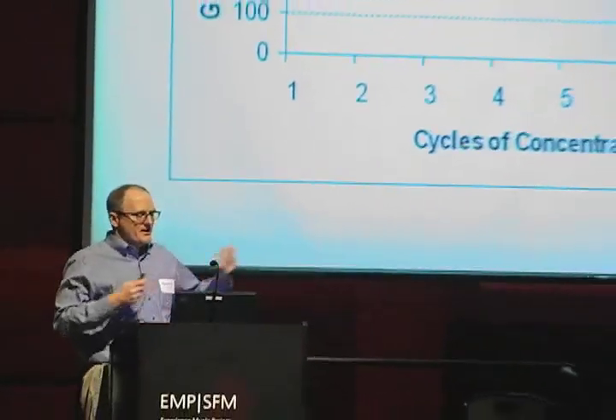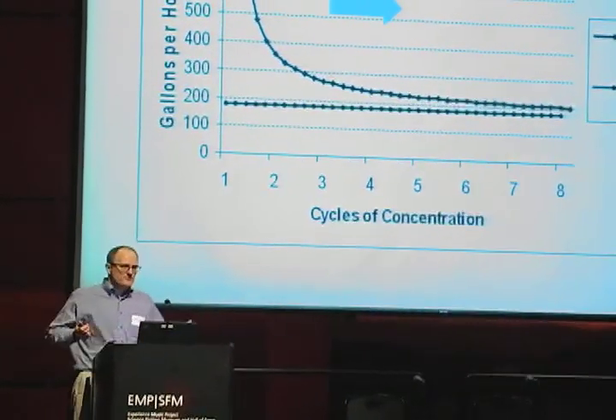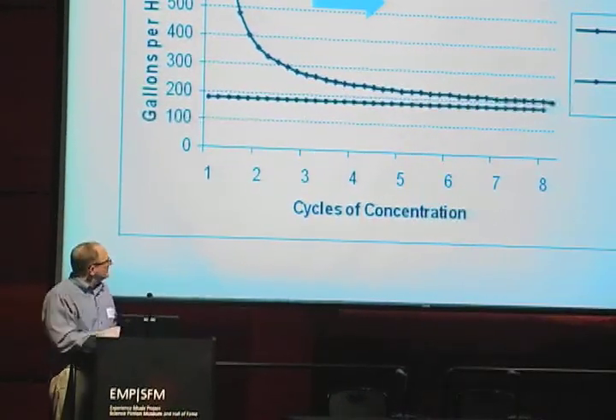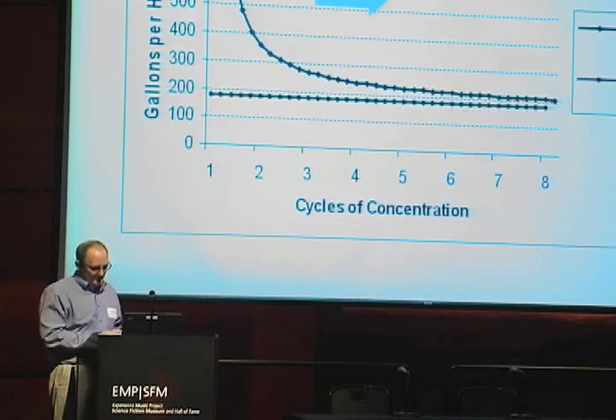But what we're talking about, and what Mike was pushing for, is we want better water treatment. In general, in the sense of water conservation, better water treatment means higher cycles, meaning reducing the additional portion of water needed to have a successful water treatment system. He discussed a target of 15 cycles, and that seems actually pretty reasonable based on my experience. But the idea is we want to push in that direction.